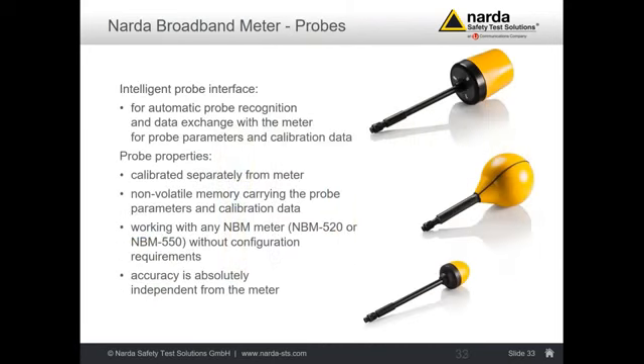So all the probes we are supplying for the NBM have an automatic probe recognition. You just plug it in and the basic meter automatically recognizes which probe is connected, and all calibration data and so on are automatically transferred into the basic meter. Also, all the uncertainties for the instrument are already worked out for any mix between probes and basic meters, so you can use any meter with any probe. The specification in the data sheet takes into account that there might be a little difference between two probes or two basic meters. This is all included, so you have full flexibility there.